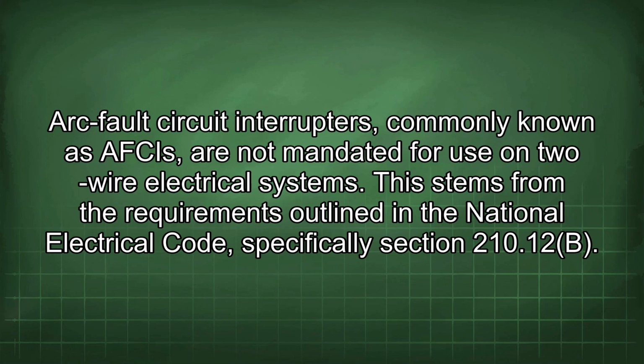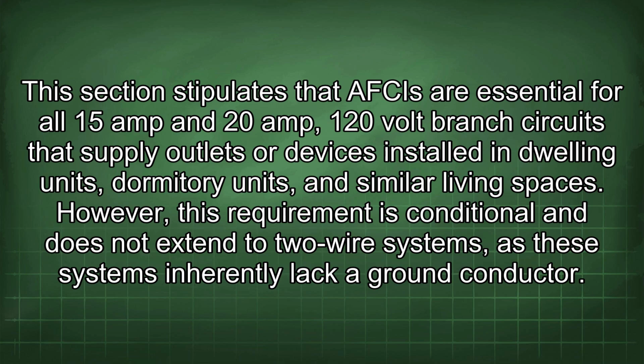Arc fault circuit interrupters, commonly known as AFCIs, are not mandated for use on two-wire electrical systems. This stems from the requirements outlined in the National Electrical Code, specifically Section 210.12(B). This section stipulates that AFCIs are essential for all 15 amp and 20 amp, 120 volt branch circuits that supply outlets or devices installed in dwelling units, dormitory units, and similar living spaces.